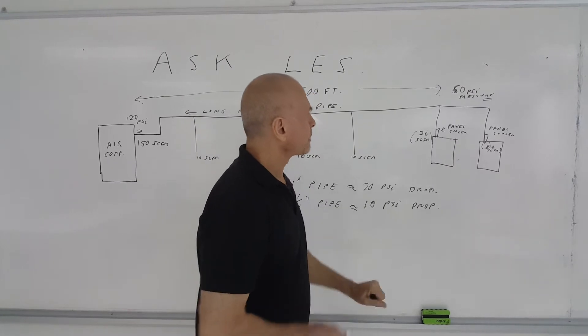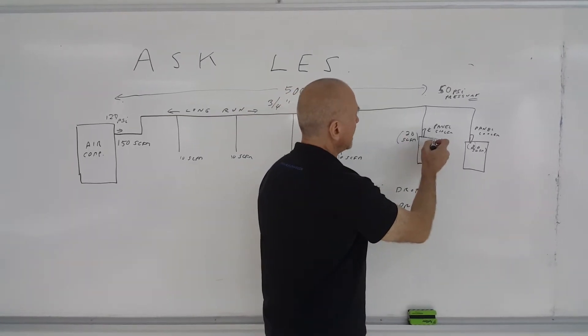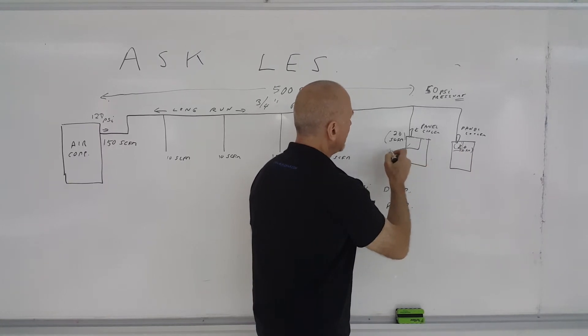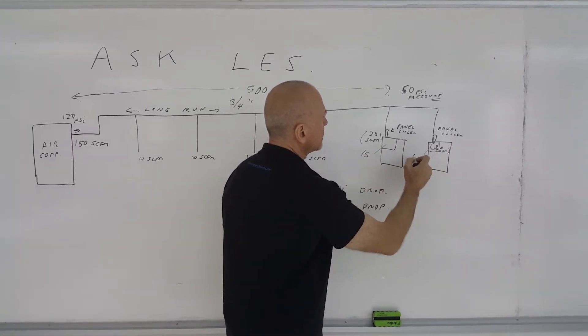So, what we ended up doing was replacing those. They isolated the hotspots in the control panels, and they ended up only needing to use 15 CFM coolers in each one.